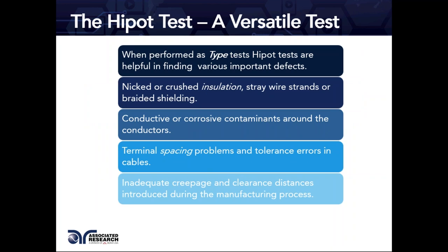The Hypot test does more than check end-user safety — it gives designers good information about product quality. As a type test during the engineering phase, the Hypot test verifies insulation quality and finds important defects such as nicked or crushed insulation, stray wire strands or braided shielding, and conductive or corrosive contaminants around conductors.